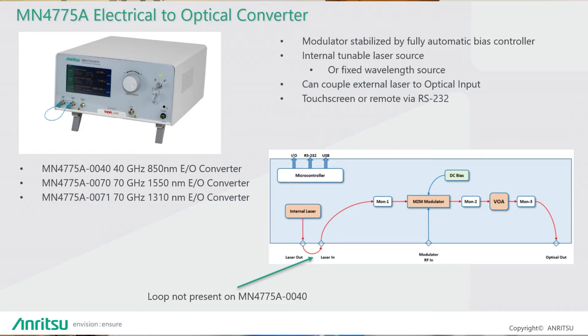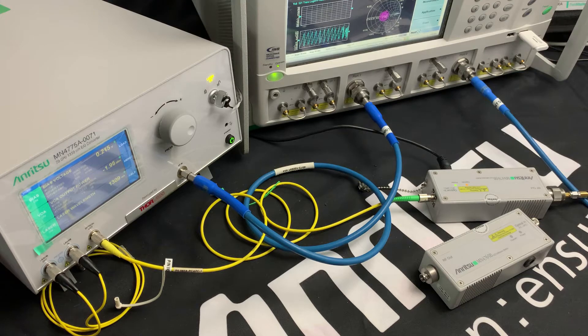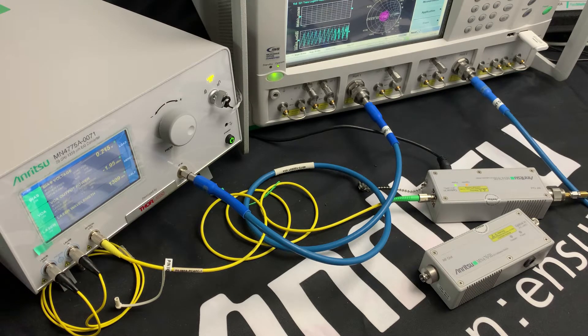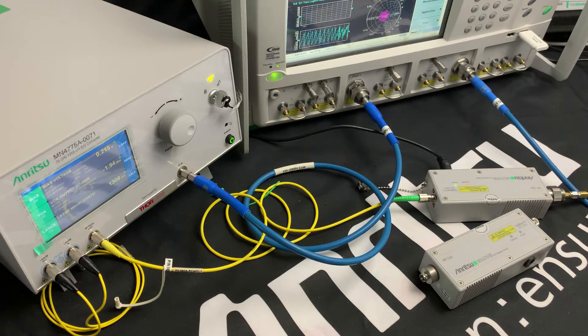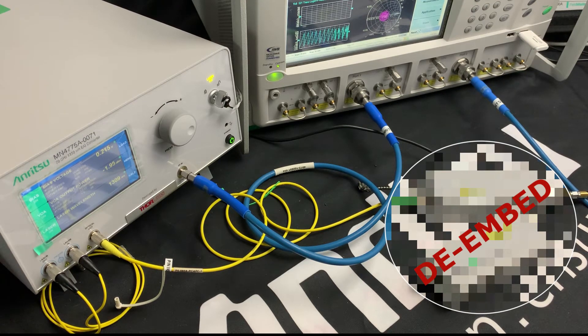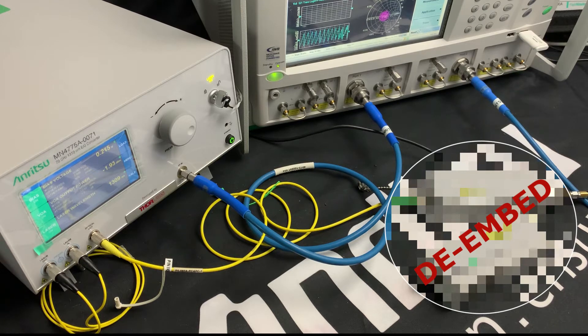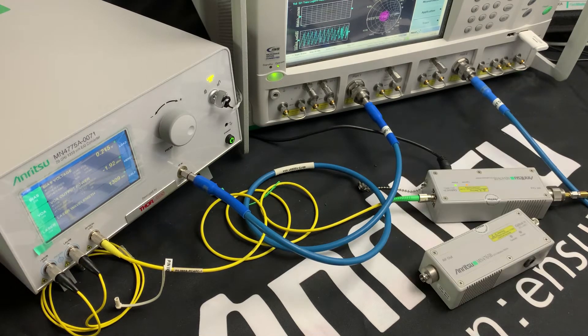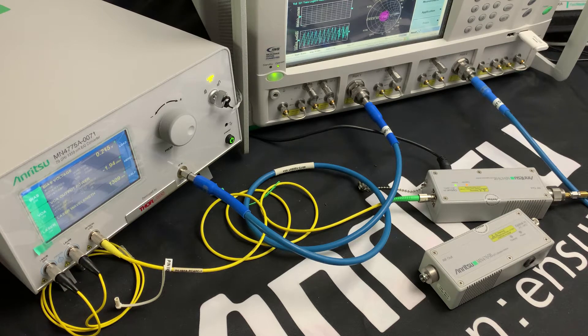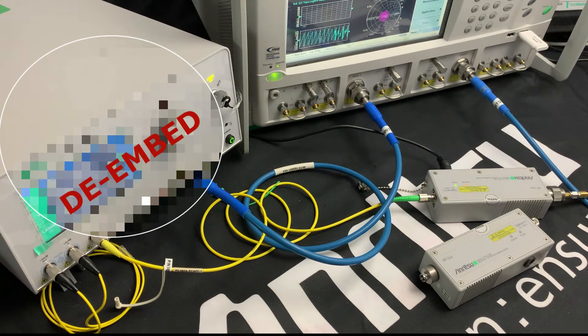Because we know the S2P files of the traceable MN4765B NIST standard, we can effectively de-embed it from the S21 measurement, giving us the response of the E2O modulator. Once we have the S2P file of the E2O modulator, we can then de-embed that also and use that to characterize subsequent photodiodes.